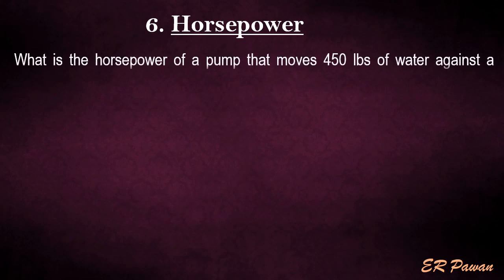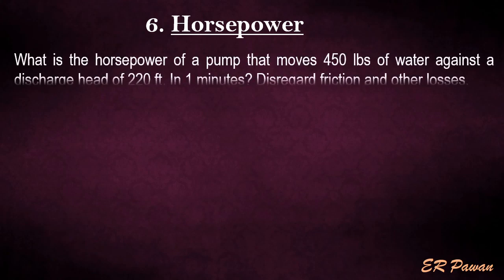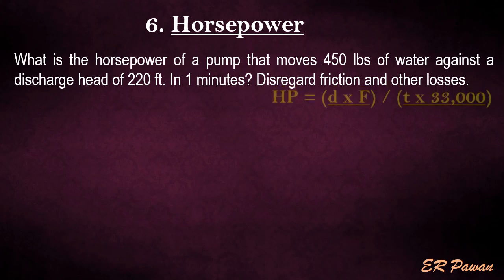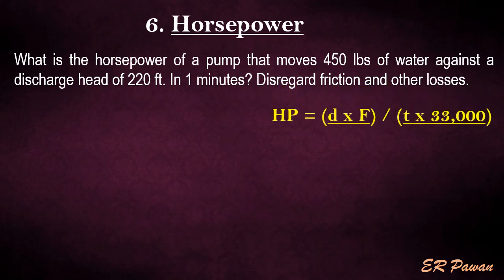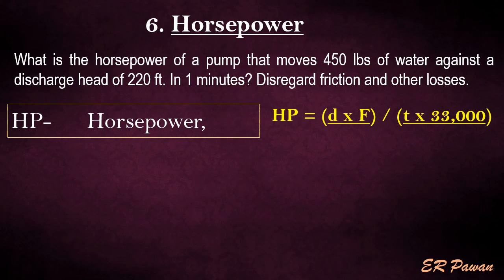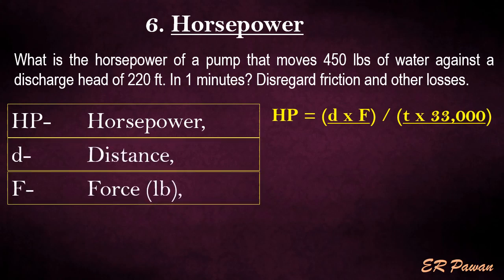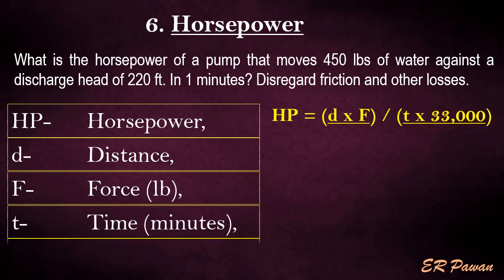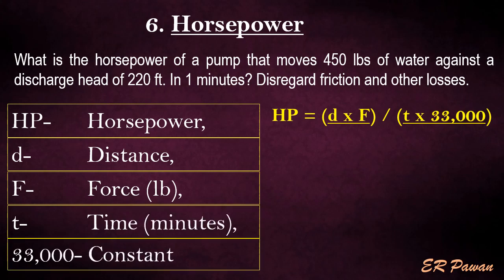Formula 6 — Horsepower. What is the horsepower of a pump that moves 450 pounds of water against a discharge head of 220 feet in one minute? Disregard friction and other losses. Horsepower equals distance multiplied by force divided by time multiplied by 33,000. Where HP = horsepower, distance in feet, F = force in pounds, time in minutes, and 33,000 is a constant. Let's put the value in the formula.